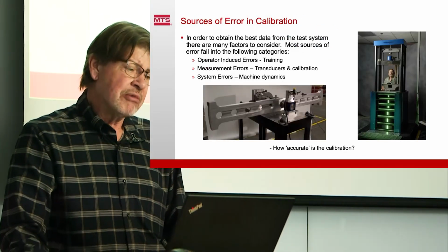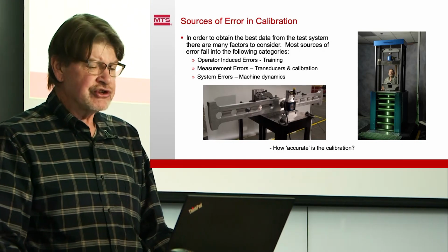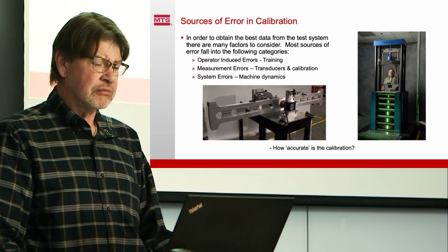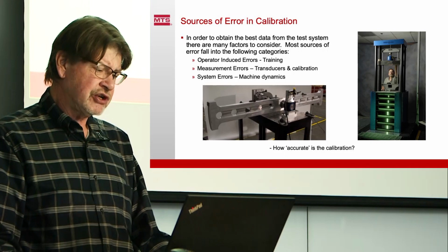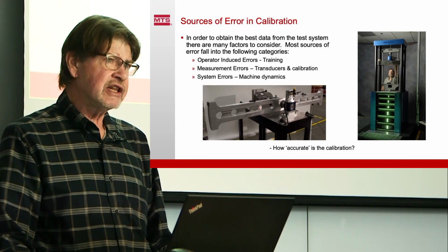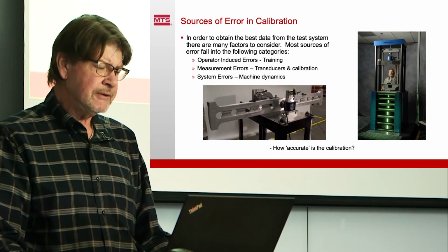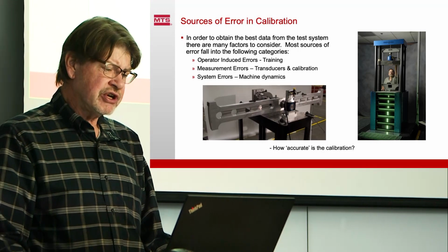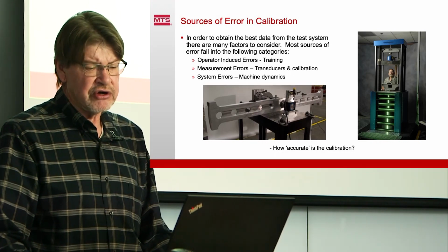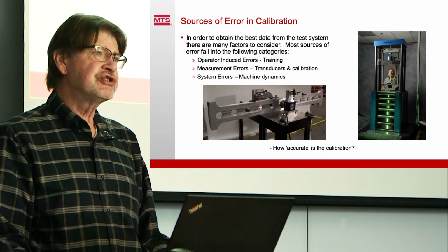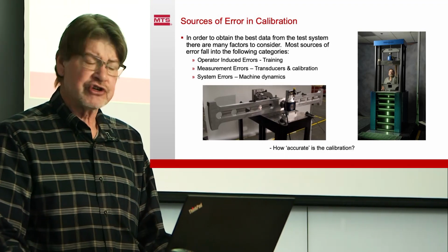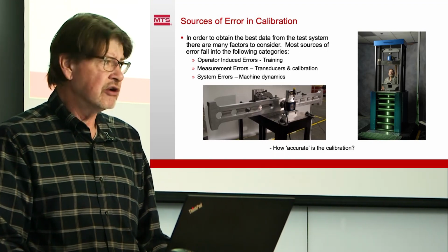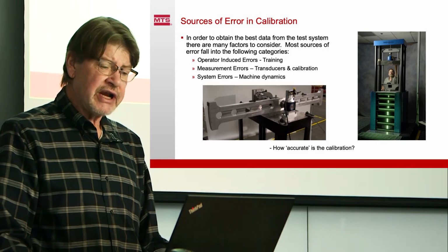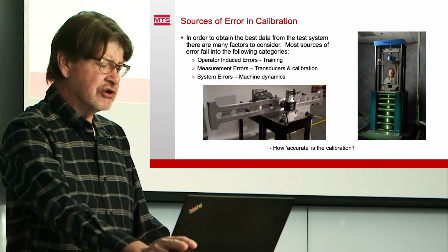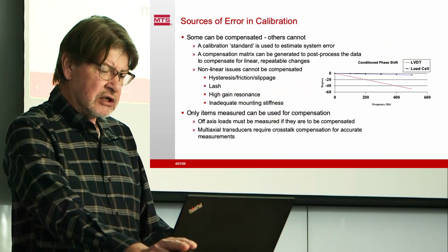Source of error in calibration. There's basically three major sources of error that we get in calibrations. One is in training, making sure that everybody knows exactly what they're doing and how to do it properly. And we can have errors in the transducers themselves, measurement errors. We can have like eccentricity or poor fixturing or friction, other things like that can make errors in our data. And machine dynamics definitely cause errors in reported data.